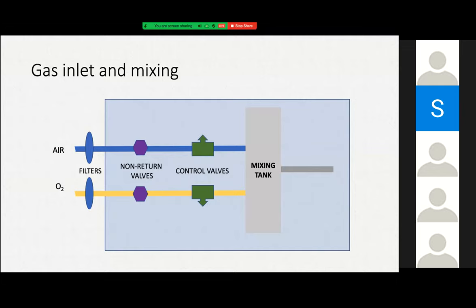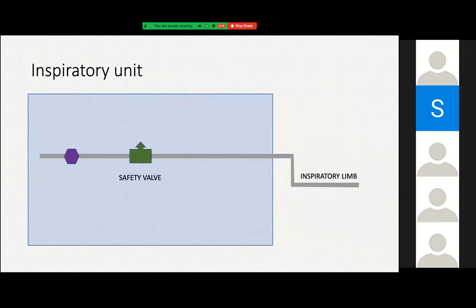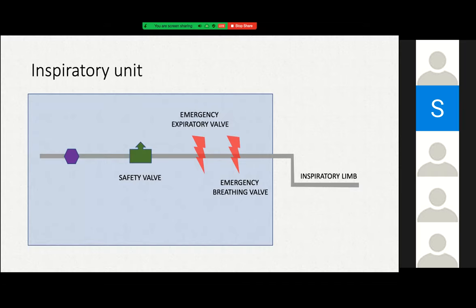The non-return and control valves are solenoid valves, which I will discuss later. Once the proportions of air and oxygen enter the mixing tank, the flow to the inspiratory limb is regulated by a mixed gas metering valve, controlled by the computer software. Beyond the regulatory valve, there is a safety valve to regulate flow into the inspiratory limb. Some ventilators also have an emergency expiratory valve and an emergency breathing valve, though their location may differ across ventilators.